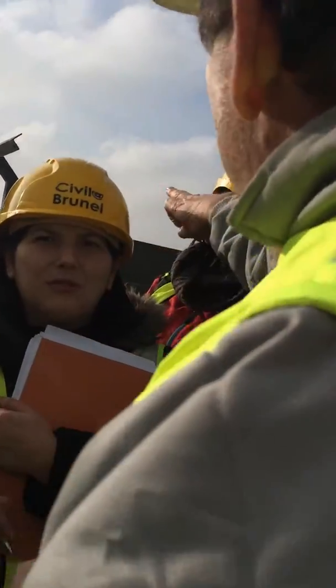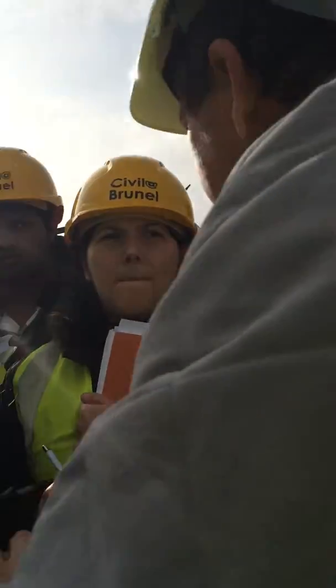So without putting numbers onto it, the biggest single running cost by a long way of any activated sludge plant is oxygen transfer. So that big building behind you, the building we walk past, is the blower house. So once we get past the anaerobic and anoxic zones, we're into aerobic treatment. To meet the oxygen demands for aerobic treatment, we need to supply air, and we can see on the surface now that there's air being introduced at the bottom of the tank.